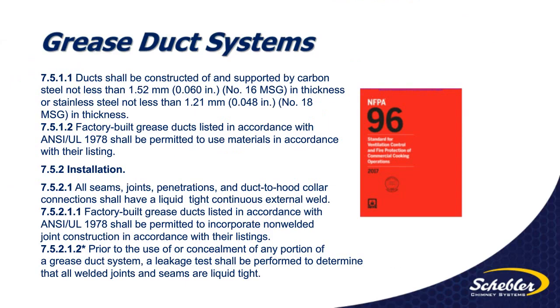Now, if we look at NFPA and what it states about construction of the ductwork, it's pretty much going to reiterate what our Mechanical Code says. Have another reference back into UL 1978. It is going to be a little more talking about seams, joints, and penetrations, that they have to be a continuous liquid-tight external weld in the ductwork, not an internal. Factory-built products would be permitted to be non-welded as long as the joint construction in the field was done per their listings. And then also notes in there, prior to concealment of any portion of the grease duct, a leakage test would need to be performed to ensure that all weld joints were liquid tight.